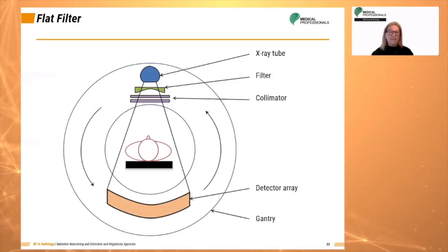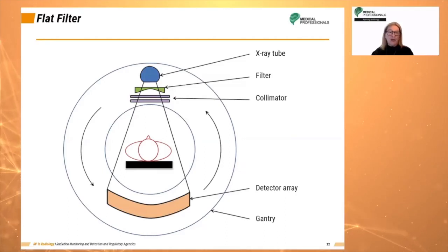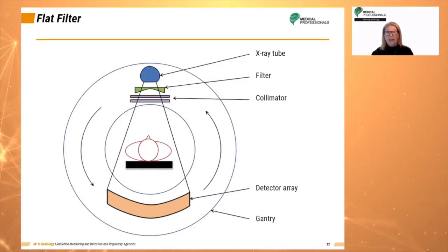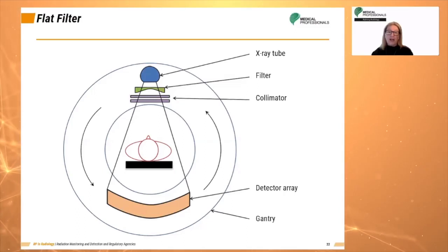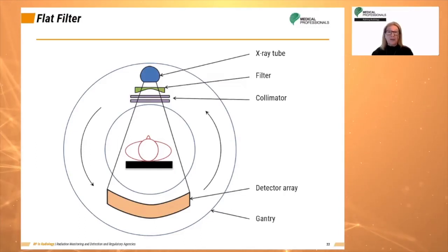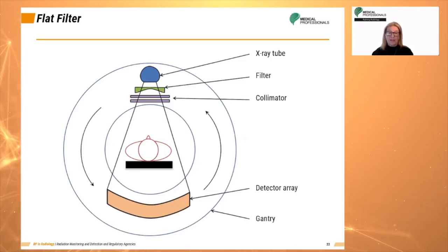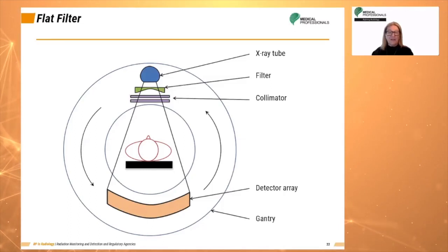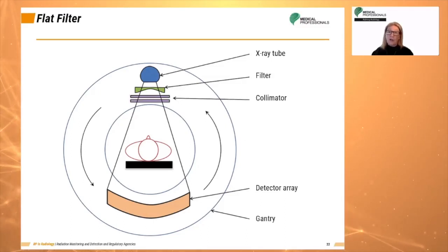CT scanners have x-ray filters that shape both the geometry and the spectrum of the beam. Standard filters are usually made of aluminum, like a radiographic tube filter, but with some important design differences. CT filters are generally thicker than radiographic filters and often combine aluminum with materials such as Teflon or copper. Flat filters attenuate low-energy x-rays, which would increase patient dose without adding to image production.